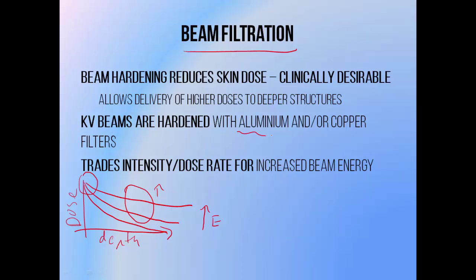While beam filtration removes low-energy components and increases average energy and depth of penetration, it also decreases the dose rate — because the more material the beam passes through, the fewer photons come out the other side. So beam filtration is a trade-off: increasing average beam energy at the expense of dose rate. If taken to extremes, it can make treatment times incredibly long. However, this ratio can be optimised through proper selection of filter materials, which will be discussed in the next tutorial on combination filters.